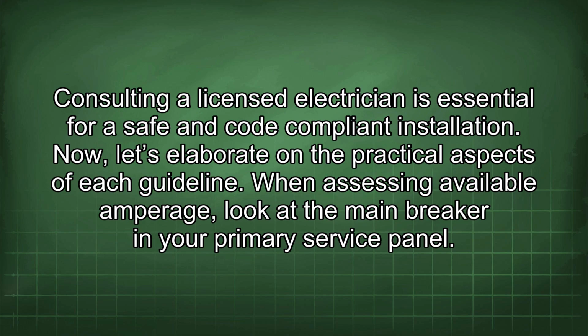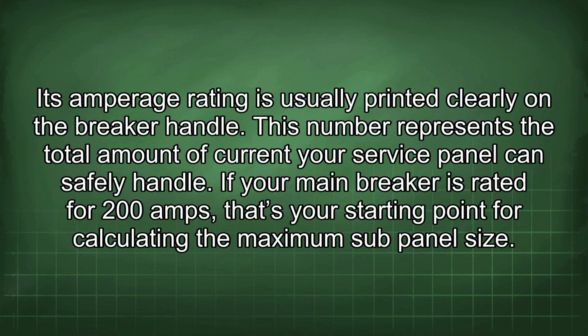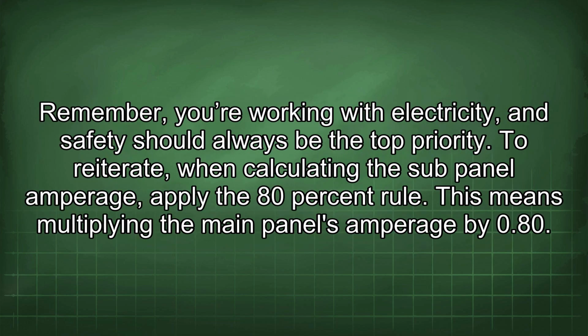When assessing available amperage, look at the main breaker in your primary service panel. Its amperage rating is usually printed clearly on the breaker handle. This number represents the total amount of current your service panel can safely handle. If your main breaker is rated for 200 amps, that's your starting point for calculating the maximum sub-panel size. Remember, you're working with electricity, and safety should always be the top priority.